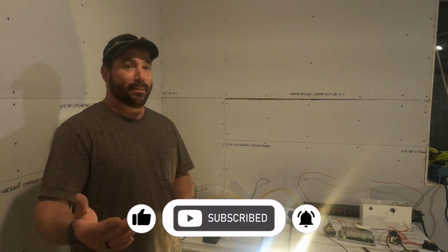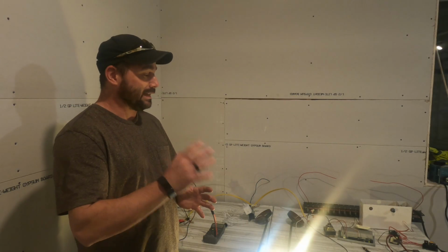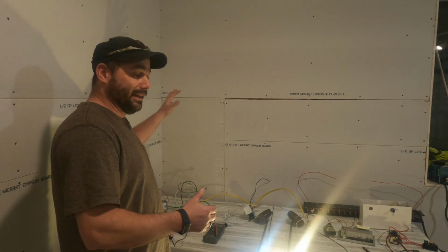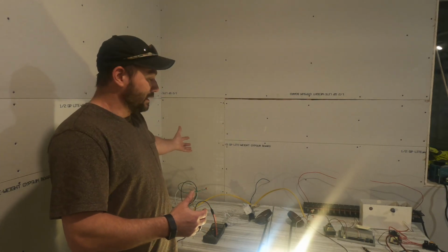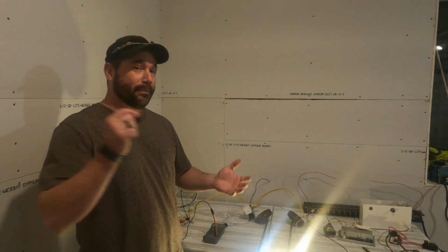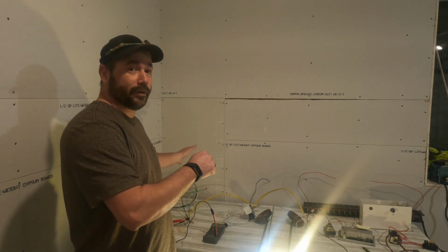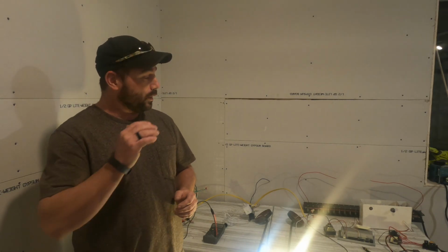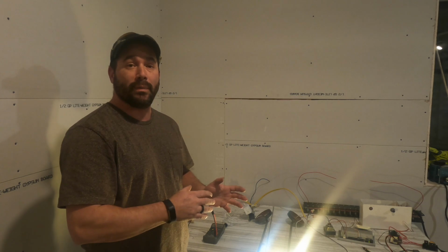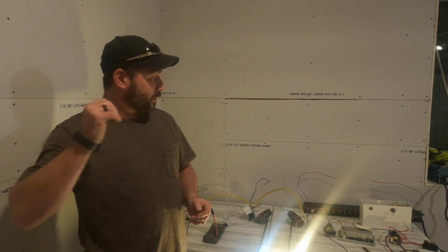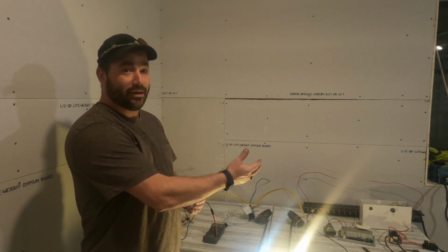Let's jump into the next piece. This thing claims that it can protect your whole house just by being connected to your panel. So we're testing that too. So it's at the end of the line on these tests. So not hitting the panel first, which would be hitting it first, shunting to ground. We're hitting at the end of the line, which would be your house side. And we're hitting all these voltages on the house side.